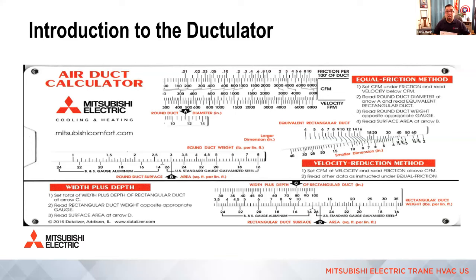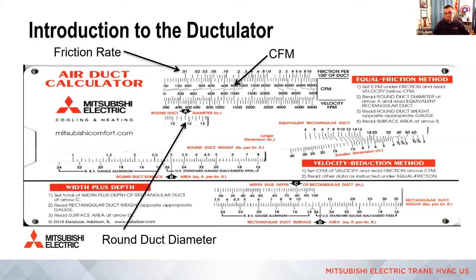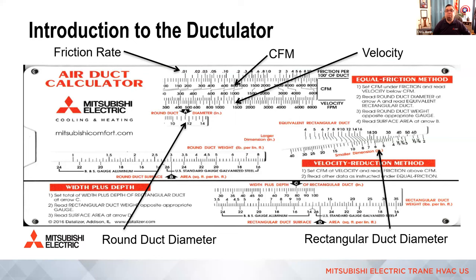Same information on here. You can see friction rate is printed on the top. We would line that up with the volume of air in the window. And then, of course, it'll tell you round duct diameter for A in that A arrow in the middle, rectangular duct diameter on the right-hand side. And then, of course, we can verify velocity on the bottom side of that window. So all the same information, just in a different format.